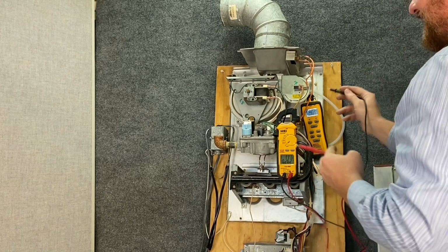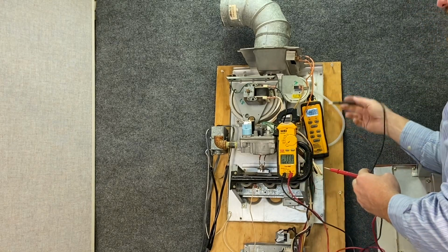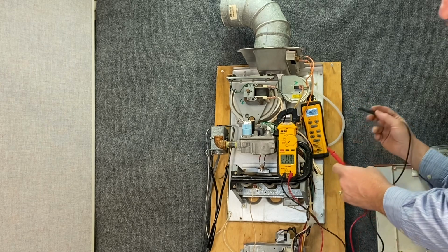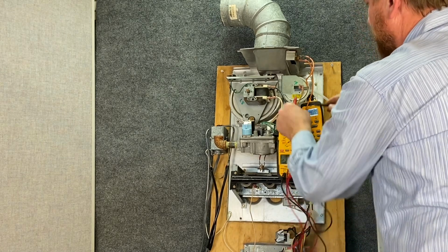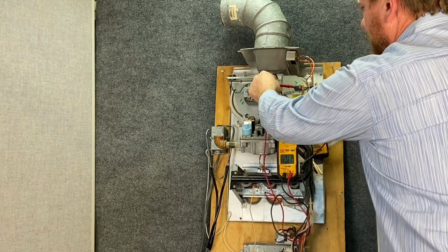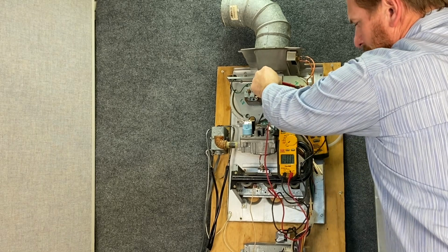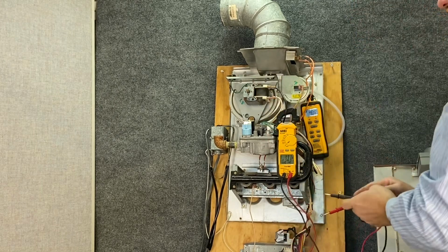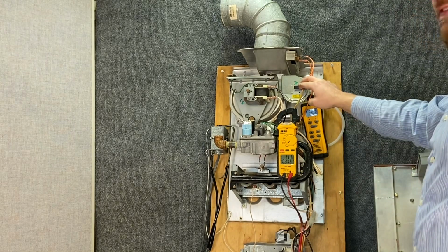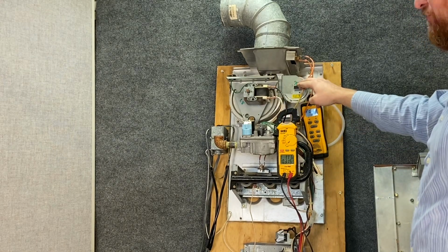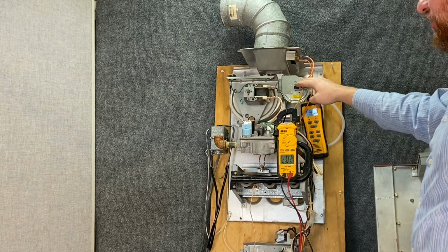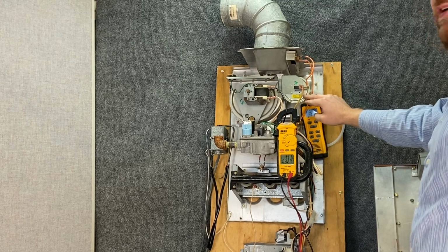If I get any kind of voltage at all, the switch is open. If I'm showing 0 volts, the switch is closed. So my bottom number is reading voltage, one on one side, one on the other, and I'm showing 27 volts. So that means that this switch is open. I'm pulling enough vacuum to the switch, but the switch is not closing. So now I need to look at the switch and see what's going on with that.